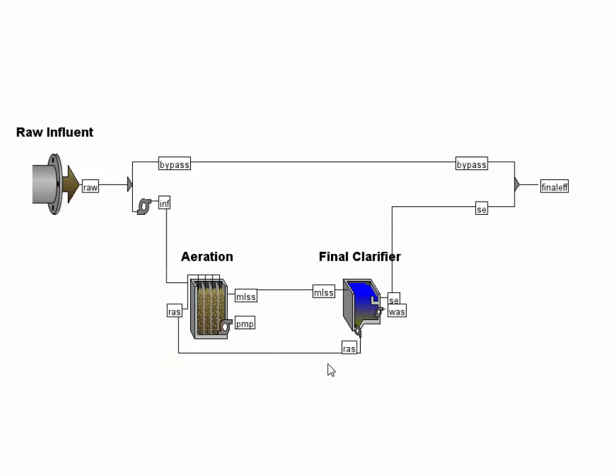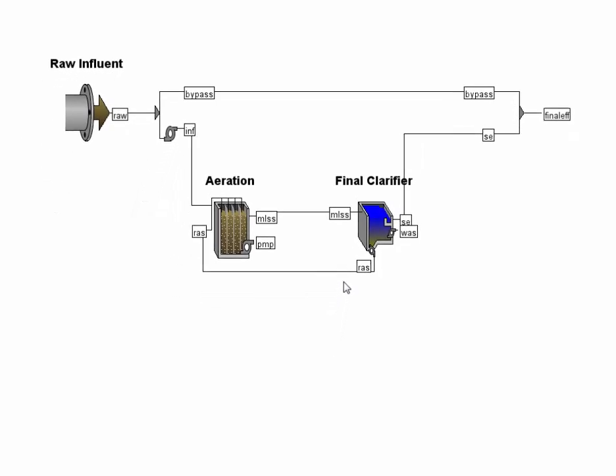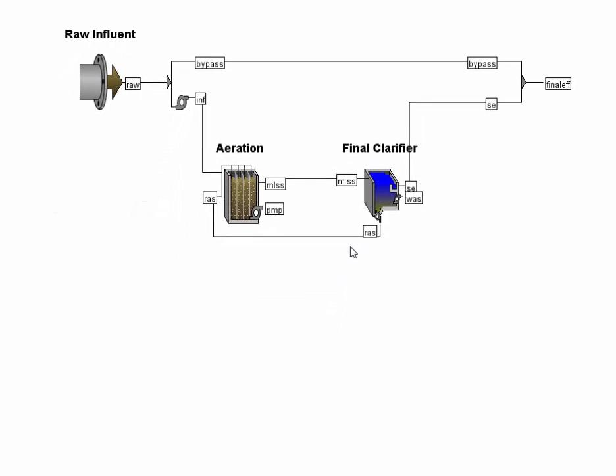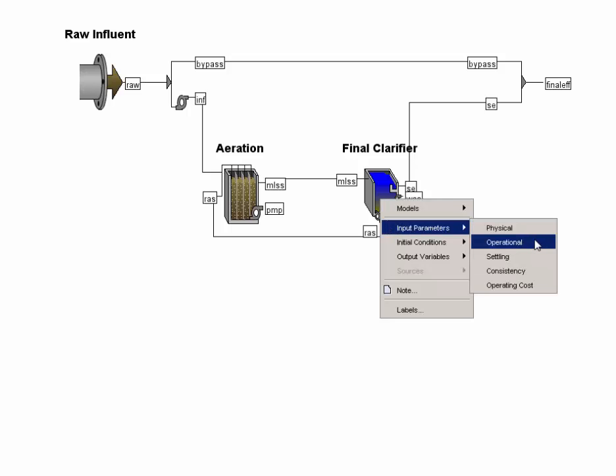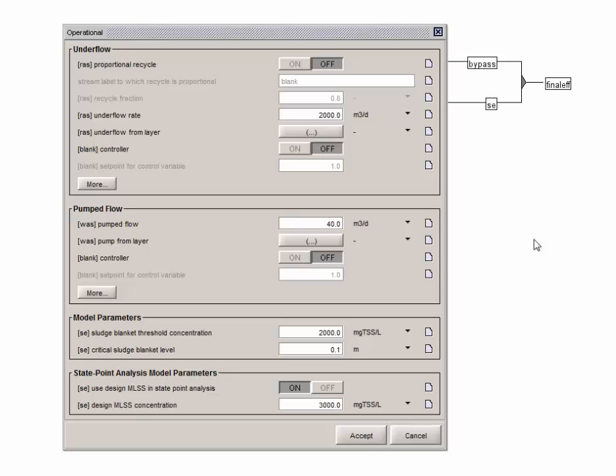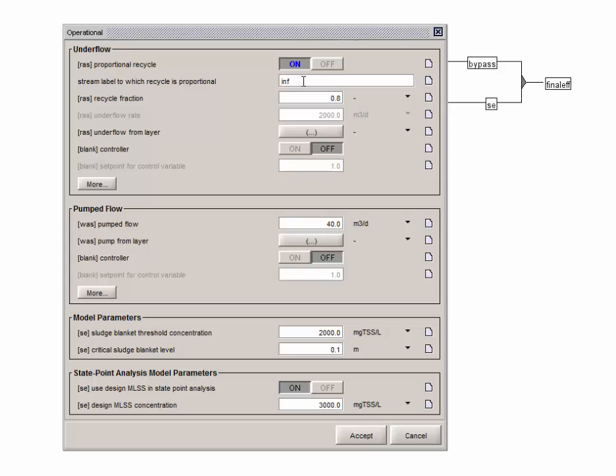Now that we have everything connected and labeled, let's set up the clarifier's operational parameters. First, we are going to want to change the recycle fraction to 80% of the influent flow rate. To do this, right-click on the final clarifier and select operational from the input parameters menu. Switch proportional recycle on. We are going to want to make the recycle flow proportional to the influent flow, so change the stream label to which the recycle is proportional to the name of our influent stream, in our case, INF.